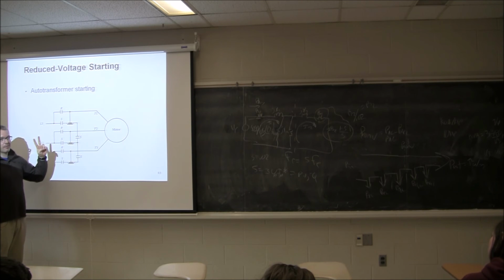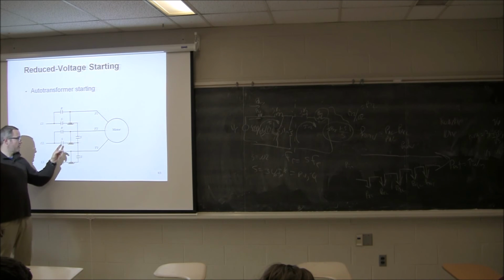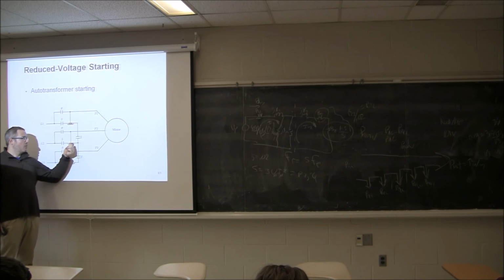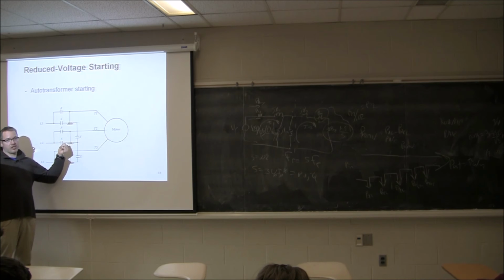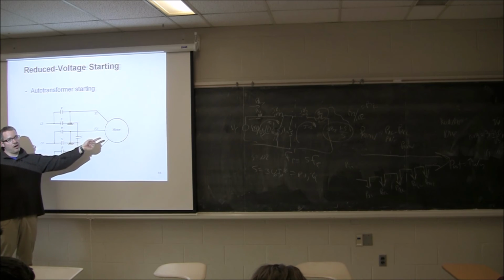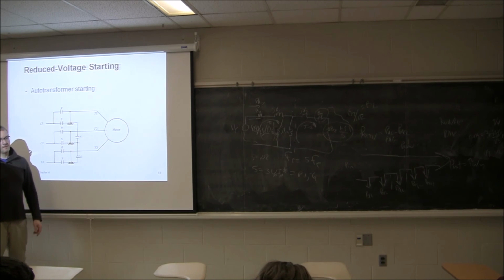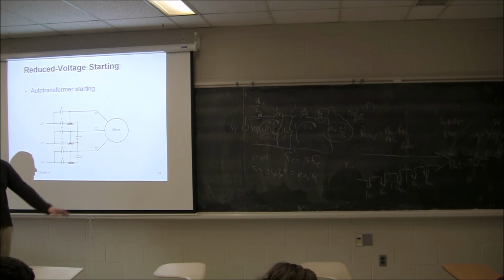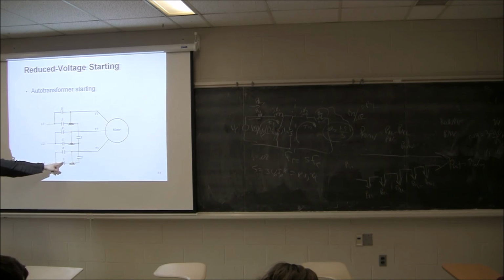There are two separate windings here. Here is the primary winding, and the secondary winding, you're scaling it up. So what they do is the current is essentially in common, right? So you get the full voltage here, and then you steal off where you want to go to the motor. That's called an auto transformer. You're giving it lower than rated voltage. How it works, the S is the start and the R is the run.